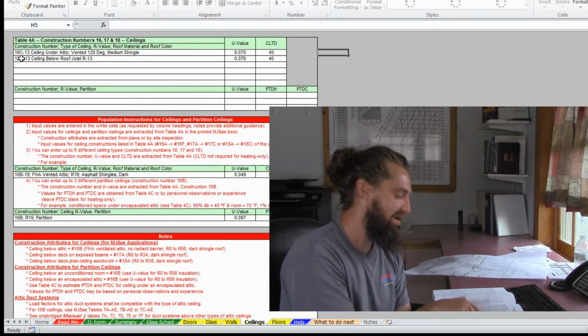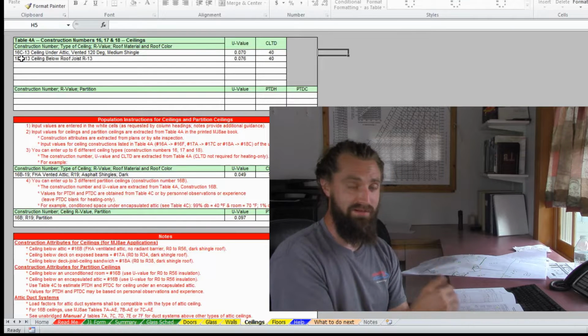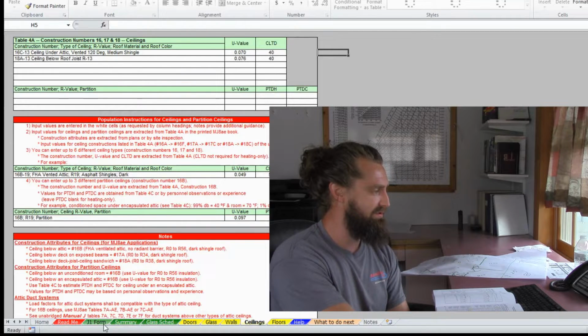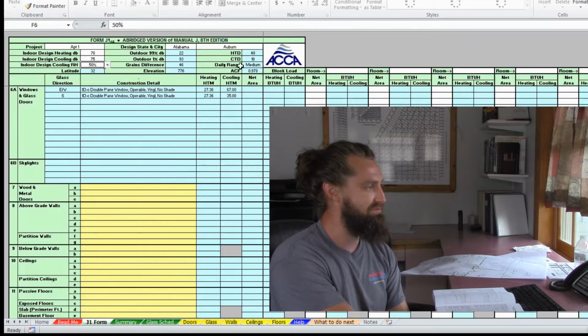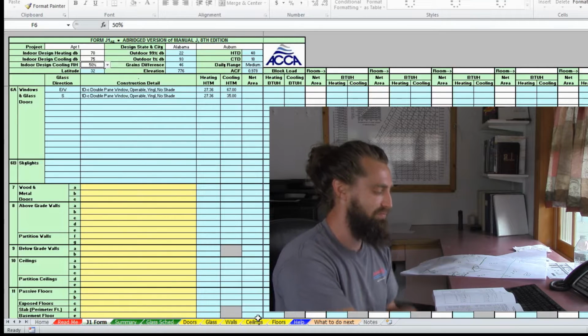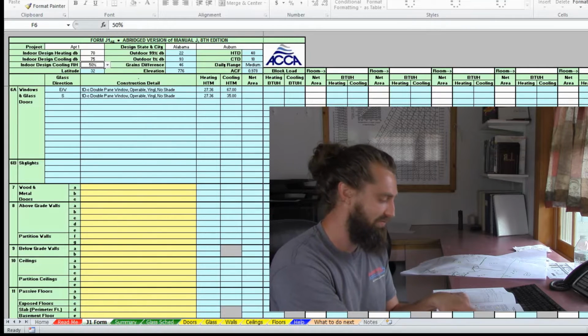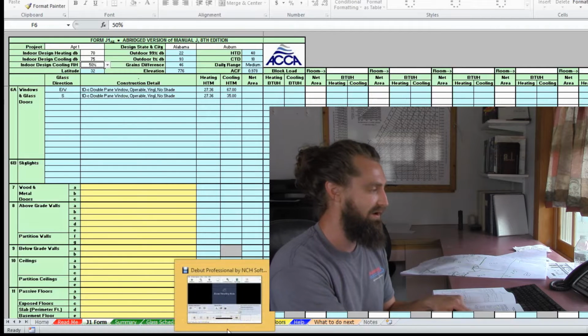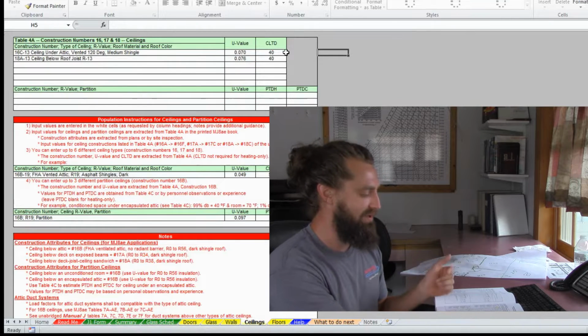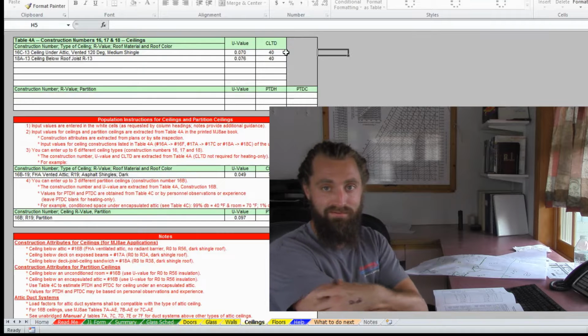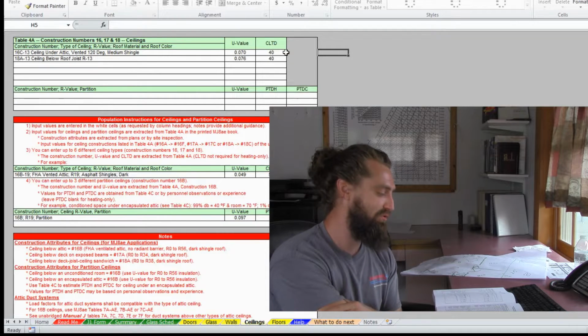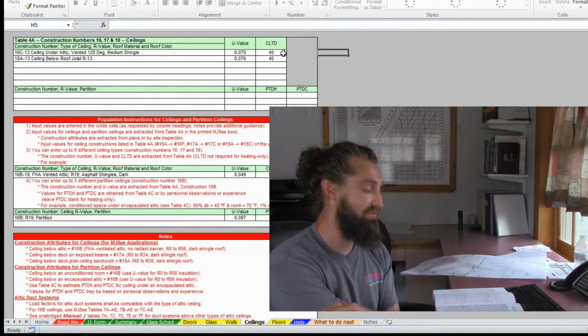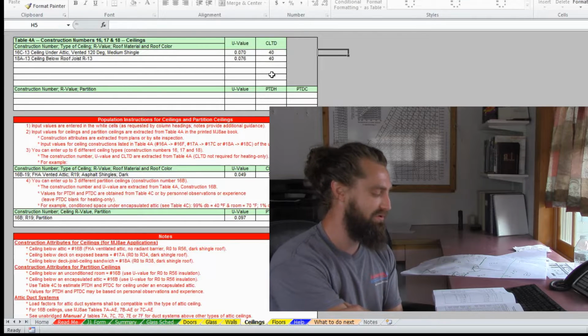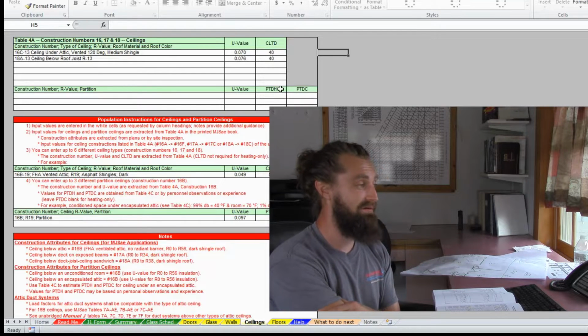Now we go across and we've got our design difference and daily range. For Auburn, Alabama, we go back to our page and we see that we've got a cooling differential of 18 and a daily range of medium. So we would look at that when determining what heat transfer multiplier we would use for our ceiling. Now I used 40 because in Pennsylvania we have a 15 degree cooling design and a medium temperature range, but we could also probably bump that up to like a 45.